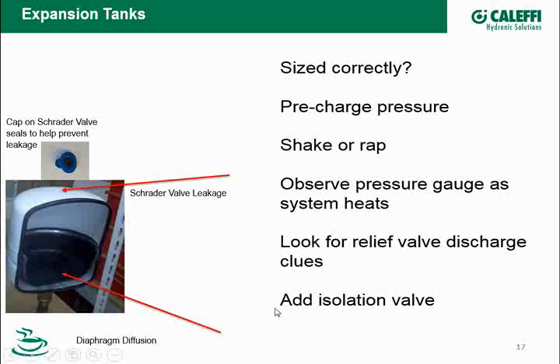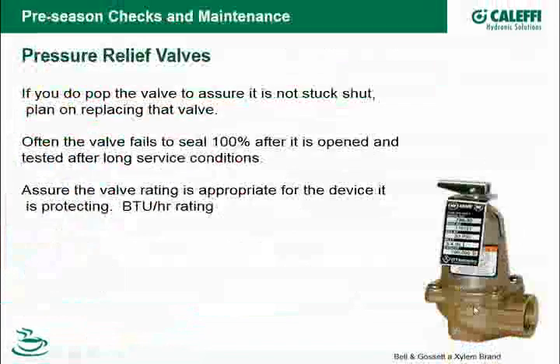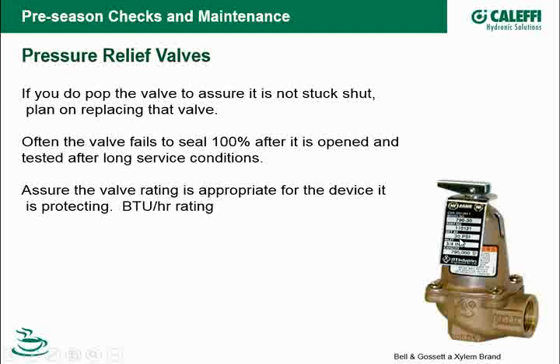You can take a fluid sample out, and they'll also have a means that you can lock the handle in the open position. Some guys will just take a crescent wrench and take the handle off and put it somewhere else on the job, so somebody's not tempted to turn that valve off and isolate the expansion tank from the system. I know Webstone, I think Taco, there's a lot of brands, Watts, I think, has a nice expansion tank isolation valve out there also. Pressure relief valves, a couple things to keep in mind. There are ratings on pressure relief valves. When you go to a job, make sure that the right valve is in there.